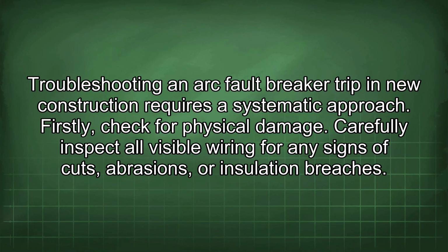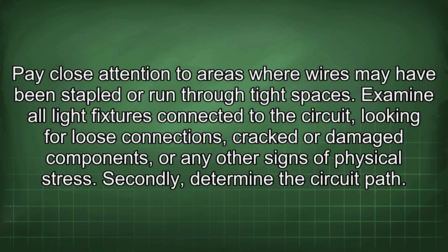Troubleshooting an arc fault breaker trip in new construction requires a systematic approach. Firstly, check for physical damage. Carefully inspect all visible wiring for any signs of cuts, abrasions, or insulation breaches. Pay close attention to areas where wires may have been stapled or run through tight spaces. Examine all light fixtures connected to the circuit, looking for loose connections, cracked or damaged components, or any other signs of physical stress.